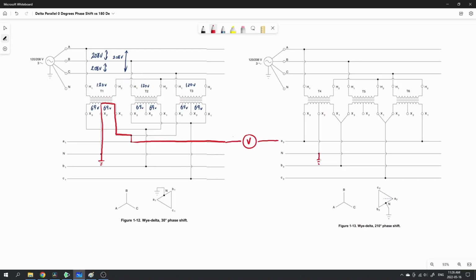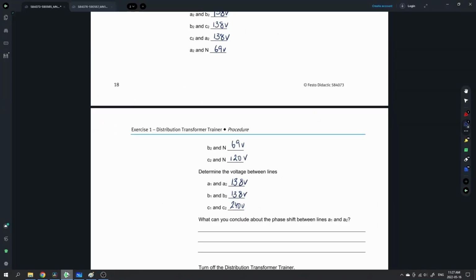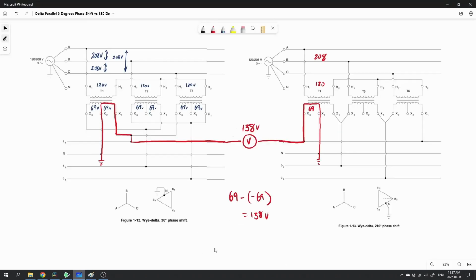Coming from the common ground, we're picking up identical voltages again. We have 208 volts as our line voltage, 120 volts on the primary, 69 volts on each of our windings, so picking up another 69 volts before coming back to the voltmeter. So we have 69 minus negative 69, giving us 138 volts from A1 to A2. Let's double check that's the same - yes, A1 to A2 was 138 volts. Excellent, so that seems to be working out.